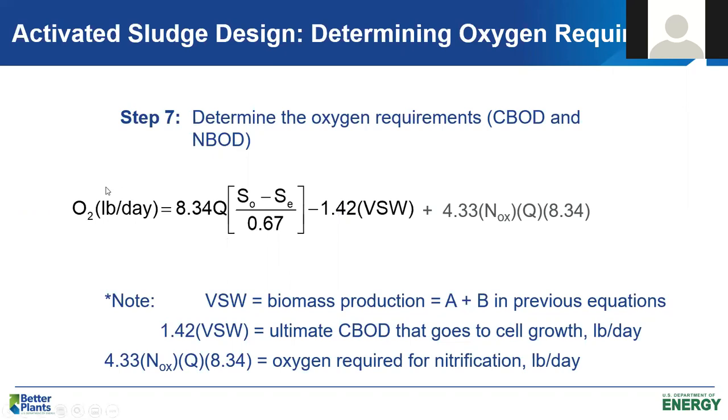So let's look at those first two components. This first term, 8.34 Q times (So minus Se) divided by 0.67, is the total ultimate carbonaceous BOD that's removed in the process. As I said, that BOD load goes into synthesis reactions, which doesn't consume oxygen, and the rest of it goes into the energy reaction that does consume oxygen.